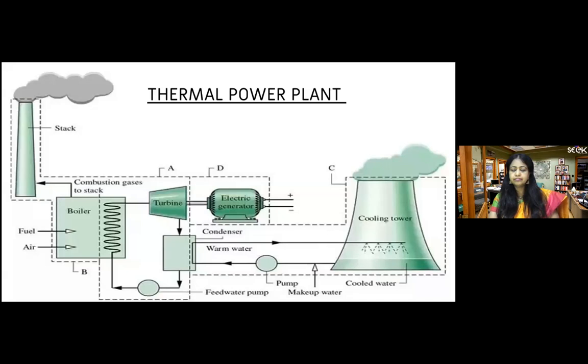So what may be the problem with the operator? If an operator is not concentrating on what is happening with the liquid level of the boiler, he verifies it at a constant frequency, maybe every 5 hours or every 2 hours, depending on the size and output of the boiler and a number of other factors. So at that fixed frequency he checks whether the water level is okay or not. If he misses doing that, imagine what will happen.